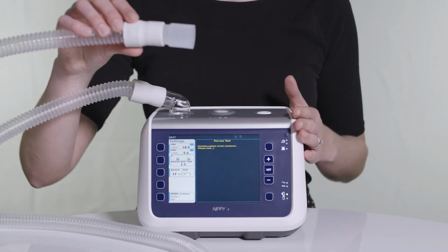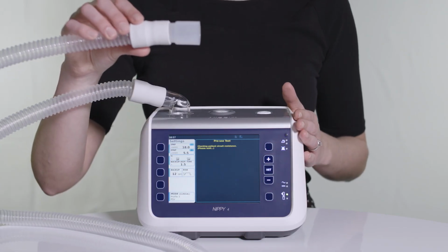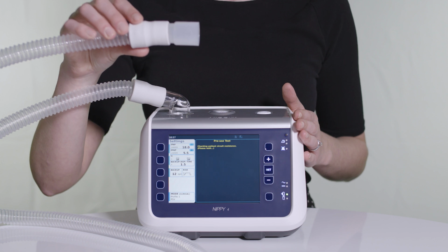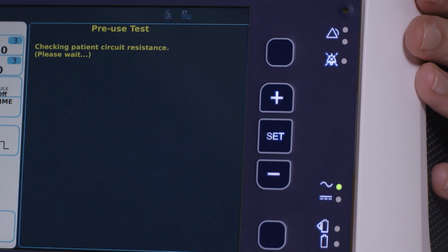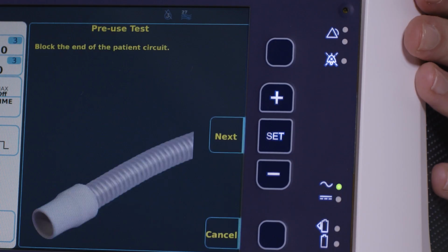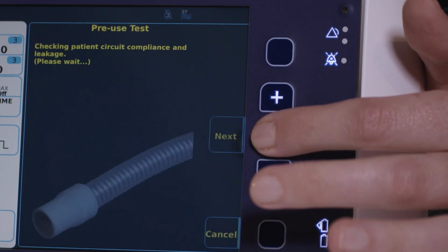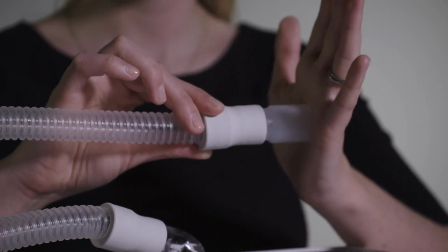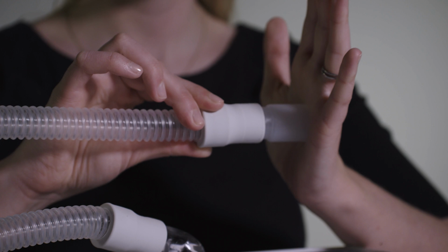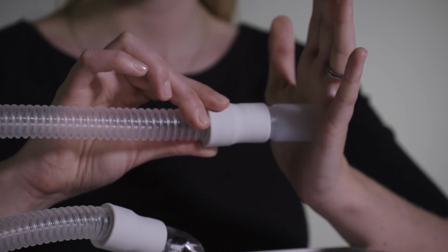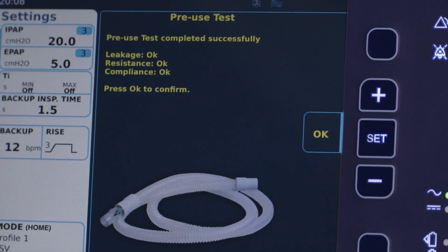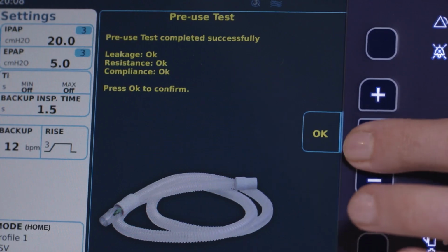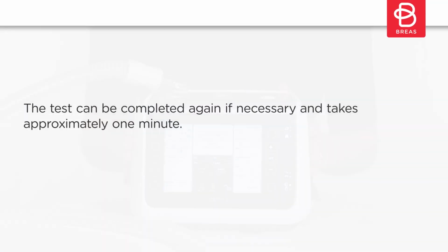Initially, air will pass through the circuit to assess the circuit resistance. Keep the end of the circuit unobstructed for this step. It will then ask you to block the end of the circuit, cover completely and maintain a seal whilst air is pushed through the circuit again. It will then tell you whether the circuit pre-use test has passed or failed. The test can be completed again if necessary and takes approximately 1 minute.